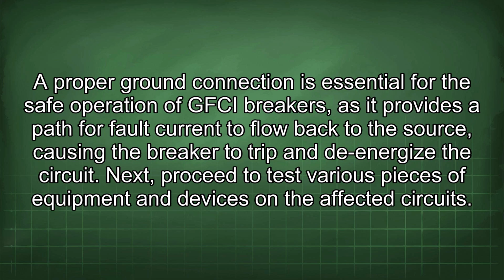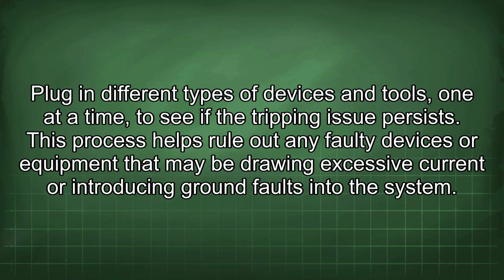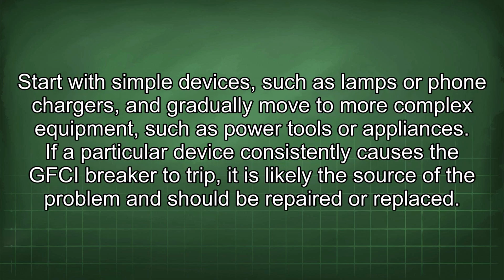Next, proceed to test various pieces of equipment and devices in the affected circuits. Plug in different types of devices and tools, one at a time, to see if the tripping issue persists. This process helps rule out any faulty devices or equipment that may be drawing excessive current or introducing ground faults into the system. Start with simple devices, such as lamps or phone chargers, and gradually move to more complex equipment, such as power tools or appliances. If a particular device consistently causes the GFCI breaker to trip, it is likely the source of the problem and should be repaired or replaced.